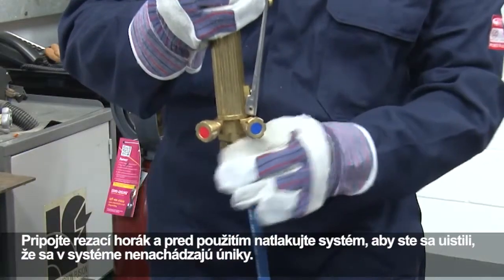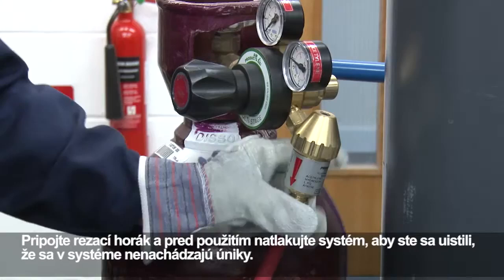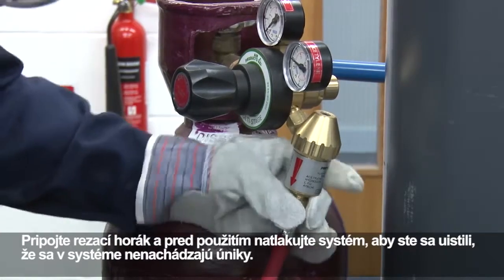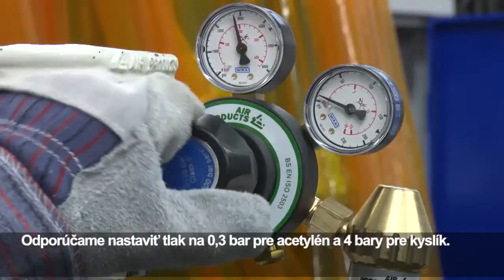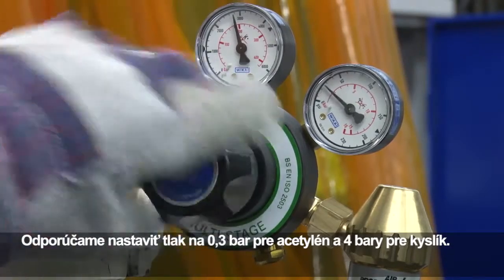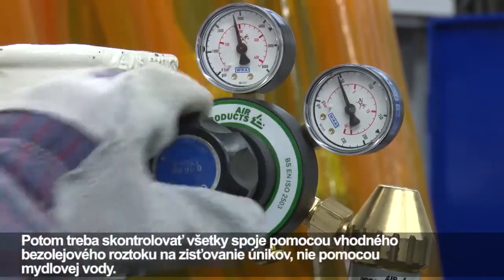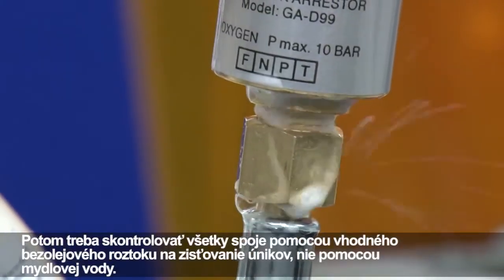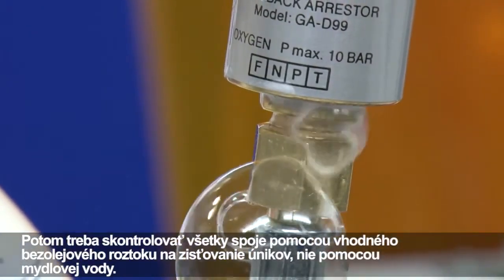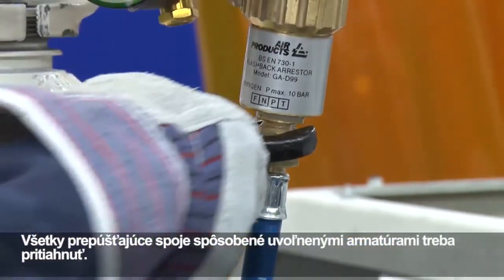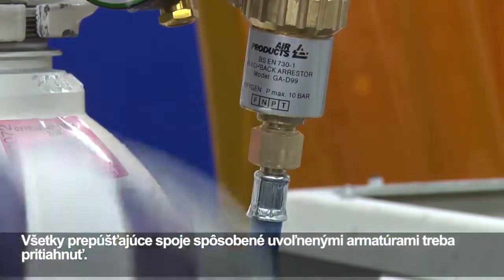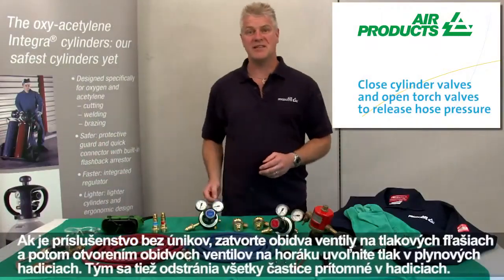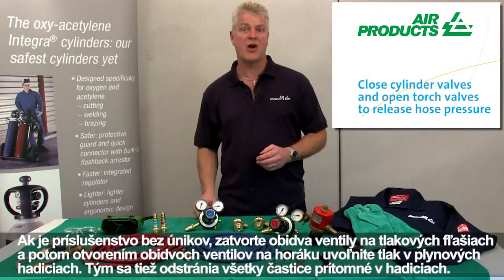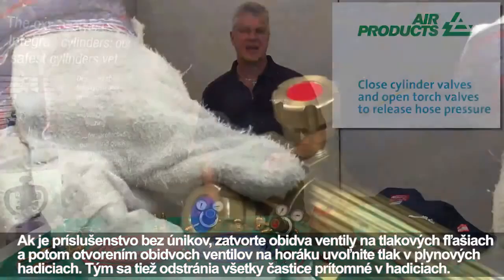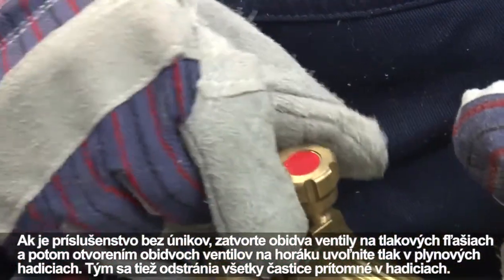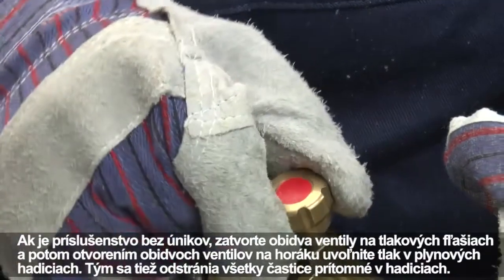Connect the cutting torch and pressurise the system before use to ensure the system is leak-free. We recommend setting the pressures to 0.3 bar for acetylene and 4 bar for oxygen. All joints should be checked using a suitable oil-free leak detection solution, not soapy water. Any leaking joints caused by loose fittings should be tightened. If the equipment is leak tight, close both cylinder valves and then open both torch valves to release pressure in the gas hoses. This also will remove any particles present in the hoses.